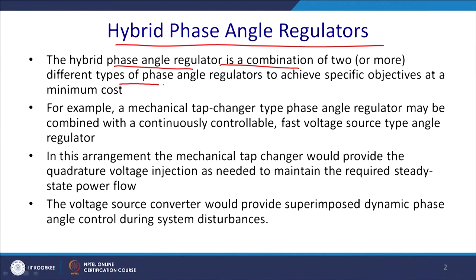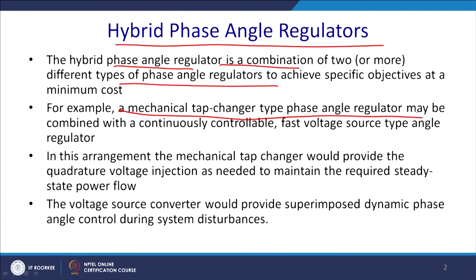In that case, we consider a hybrid phase angle regulator. A hybrid phase angle regulator is a combination of, maybe, one injecting in phase and another injecting in quadrature or any other angle. Two or more different types of phase angle regulator are combined to achieve the specific objective at minimum cost. For example, a mechanical tap changer type phase angle regulator may be combined with a continuously controllable fast voltage source type angle regulator. There we can use a space vector, so that we correctly calculate the magnitude of the voltage and the phase required and inject that. The mechanical version of it is the mechanical tap changer type phase angle regulator.